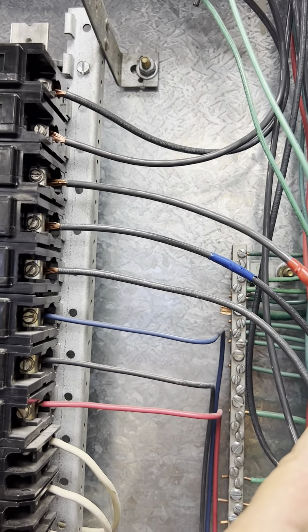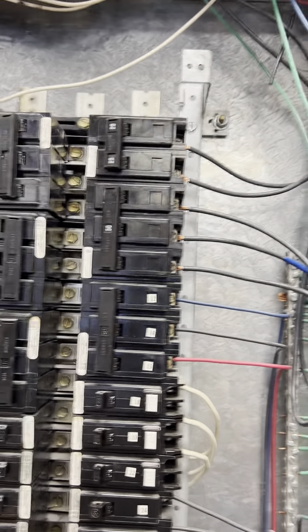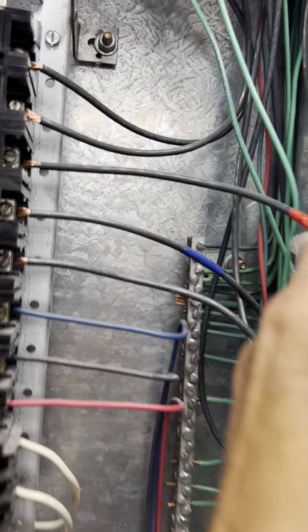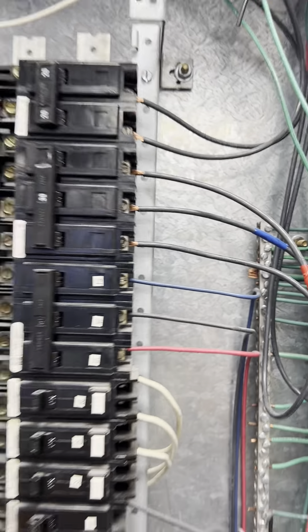We are going to change these out, and on three-phase you want to pay attention to the way it's wired in, because if you swap one lead it will try to run backwards. So we're going to wire it right — we're going to have the red wire up top, blue wire in the middle, and the next wire on the bottom.